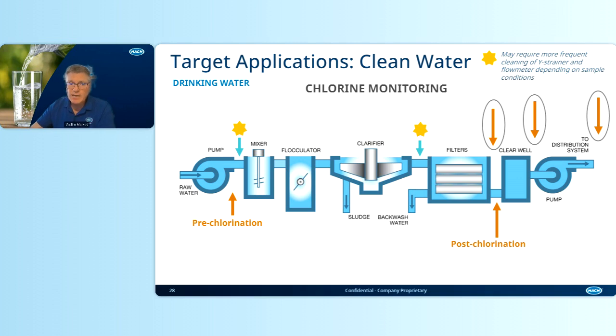Now let's talk about pre-chlorination. On the left-hand side, you can see the pre-chlorination, when the instrument can be used right there before adding the coagulant to measure the residual concentration of the chlorine injected in the raw water. It can also be used in the middle of the process after the clarifier, on settled water, measuring the chlorine residual going into the filters. In many situations, it is necessary when the treatment process requires that.